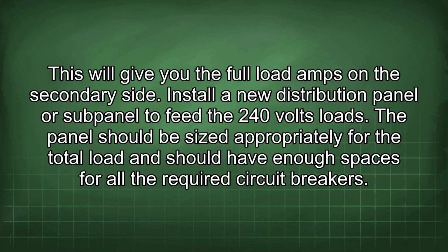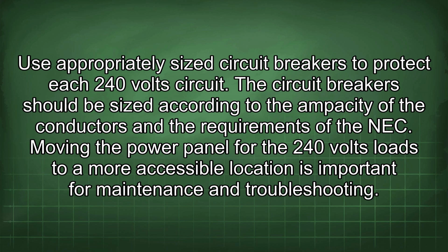Install a new distribution panel or subpanel to feed the 240 volts loads. The panel should be sized appropriately for the total load and should have enough spaces for all the required circuit breakers. Use appropriately sized circuit breakers to protect each 240 volt circuit.